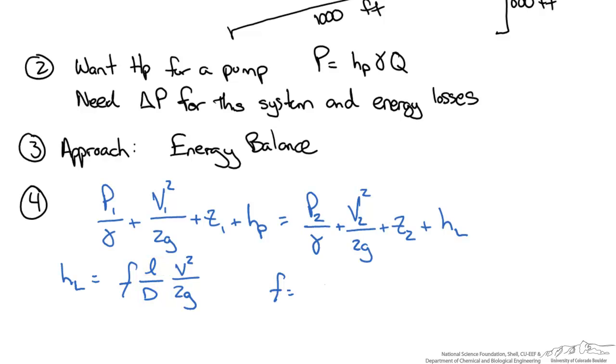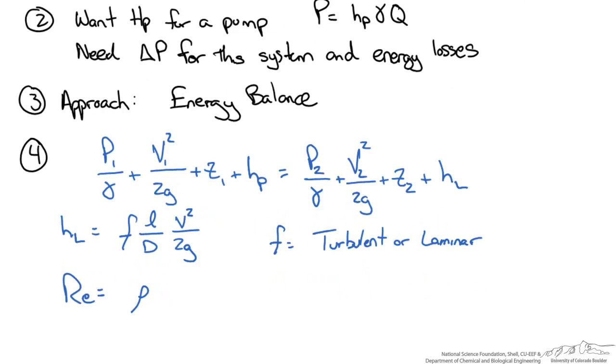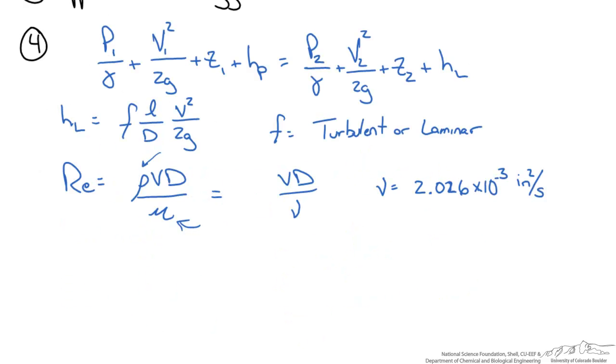The frictional factor depends on whether the flow is turbulent or laminar. We need the Reynolds number, which is a relationship of inertial forces, written as ρVD over the viscous forces, or velocity times diameter over kinematic viscosity. The kinematic viscosity for water at 10°C is 2.026 × 10⁻³ inches squared per second.